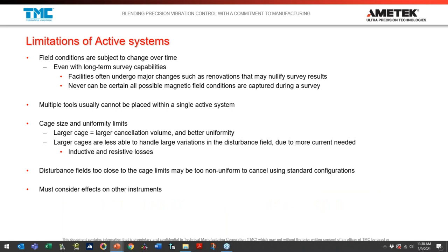Active systems do have limitations. One of the biggest is that fields change over time — magnetic fields are notorious for this because there's always construction and events that aren't captured during an initial site survey, which may become evident later. When you design a magnetic field cancellation system, you try to provide as much cancellation as possible, but you also factor in the geometry of the site, the geometry of the instrument, ergonomics for the user. You can sometimes fall into a trap because as fields change over time, one configuration may no longer work as well as another.